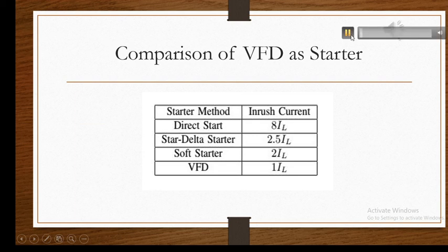The table provided here is based on experimental results in the case of an induction motor used for pumping of water in an industry. Different starter techniques were applied and their corresponding inrush currents were calculated. As you can see from the table, VFDs appear to be the best in this case, as the inrush current calculated for VFDs as starters was the least compared to others.